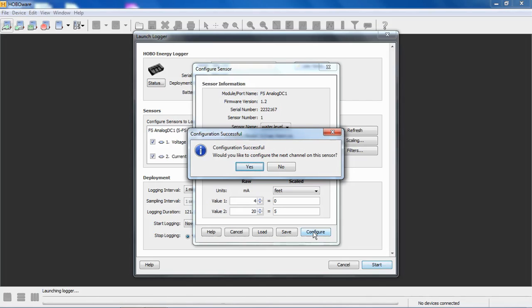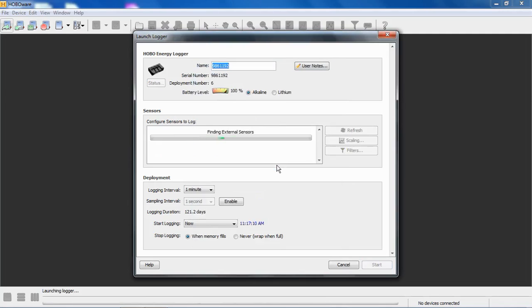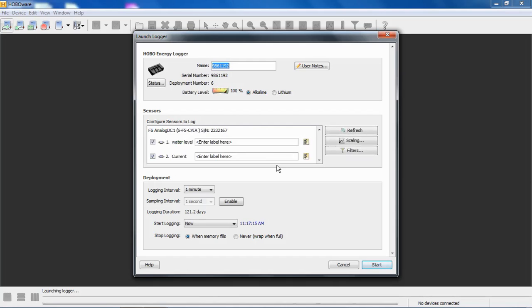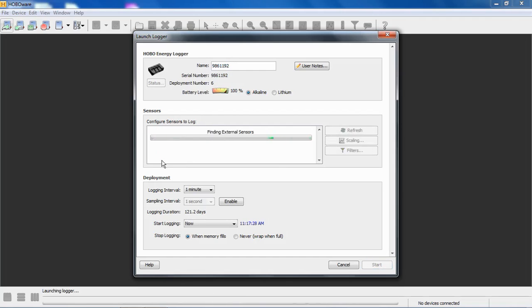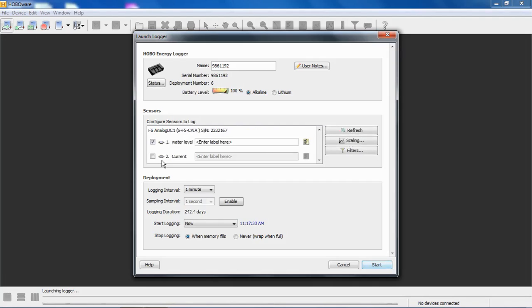Would you like to configure the next channel on this sensor? Again, if we say yes, it will take us to the second channel of this analog module for this application or this example. We'll just say no, and it will take us back to our launch screen, and we'll see now that our first channel is configured for water level. We're ready to hook up our sensor and get started with our deployment. If we're not using the second channel, we can disable it, and that will save on if you're monitoring multiple channels. Again, this logger has a limitation of 15 total data channels.